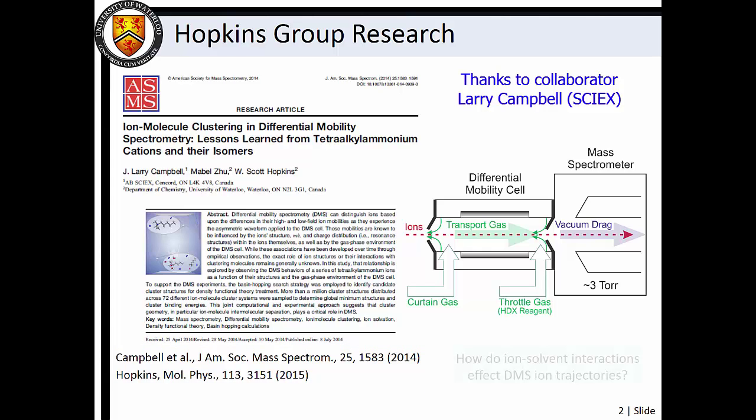Here we discuss how seeding the DMS collision environment with a low partial pressure of solvent vapor affects changes to ion differential mobility and therefore trajectory through the DMS cell.